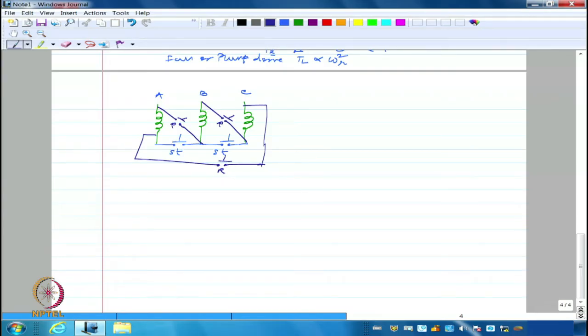But please note, when I am opening the starting contactor and later on connecting the running contactors, there is a break in the circuit for a very short while. So your load should be able to withstand that. Because it is a pump, it's all right. It's just delivering water. For a short while, if a little bit of reduction happens, heavens won't fall. So these are okay where very great accuracy is not really demanded. Right? So there will definitely be a break in the circuit when it is changing over from star to delta.